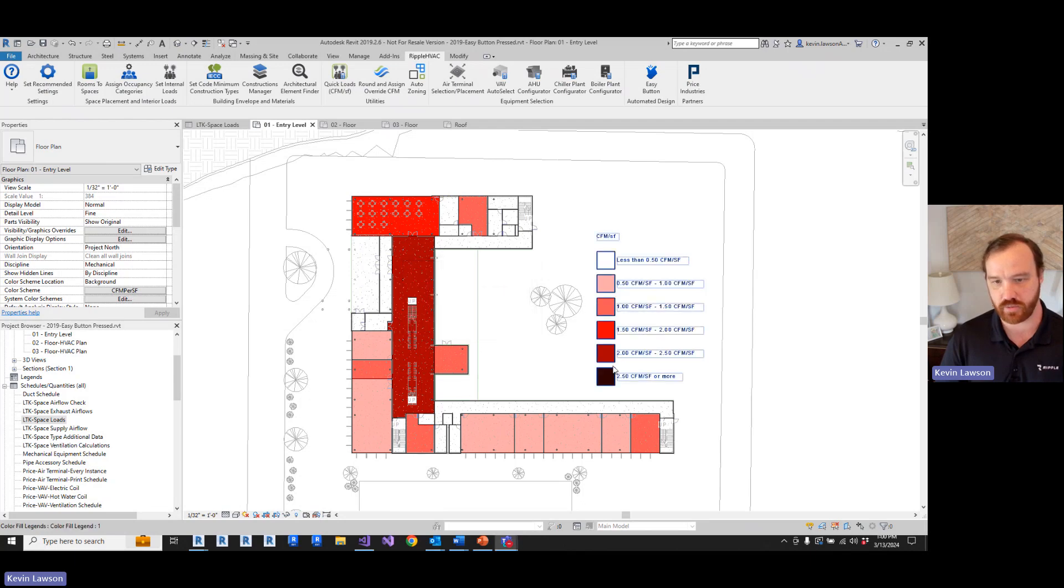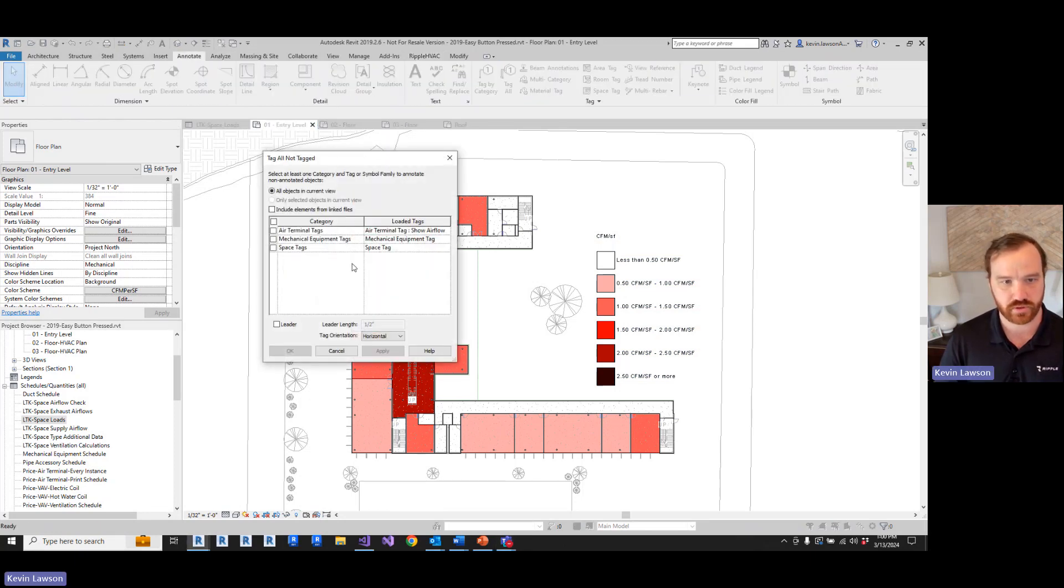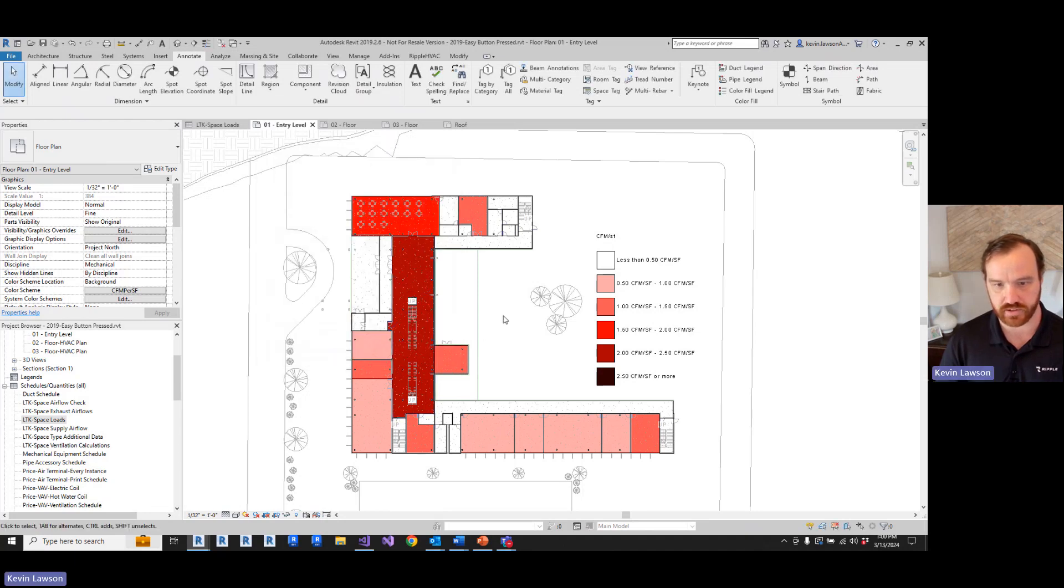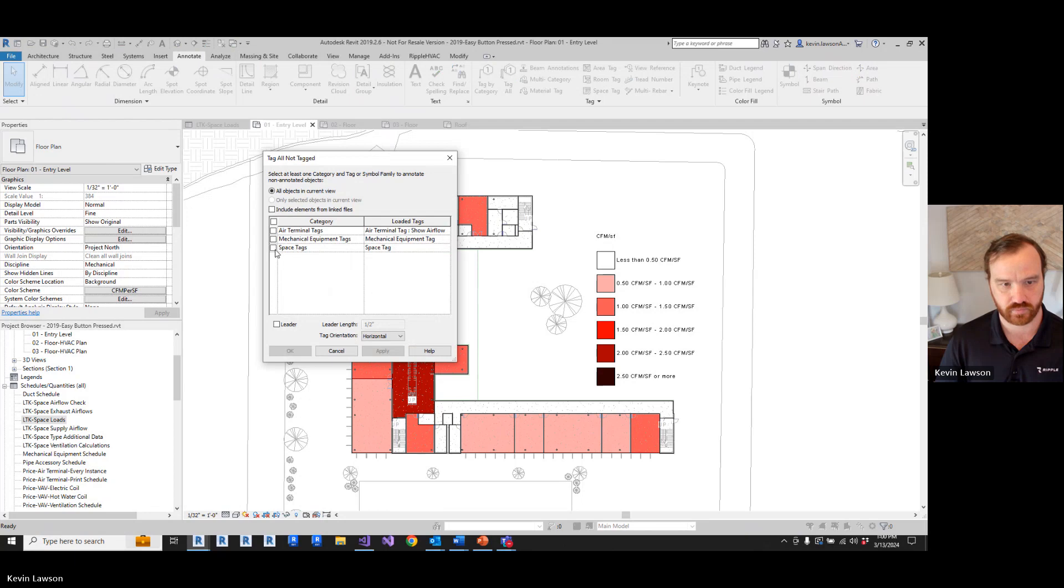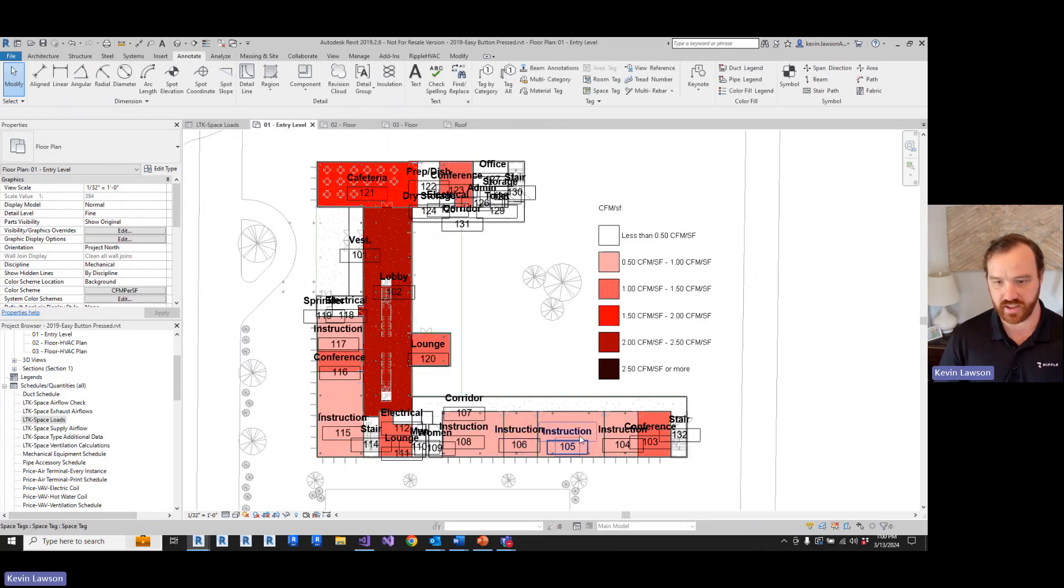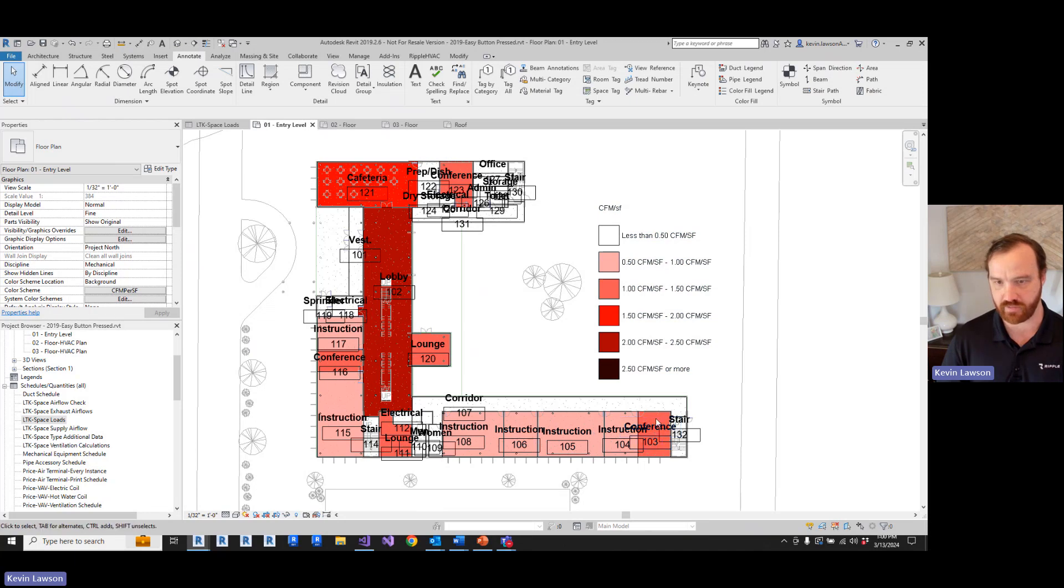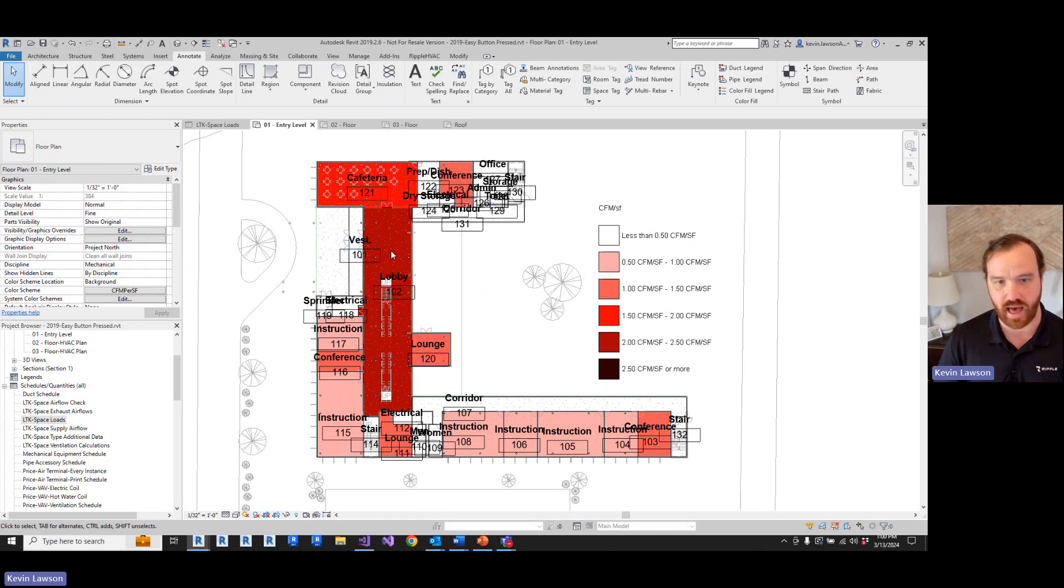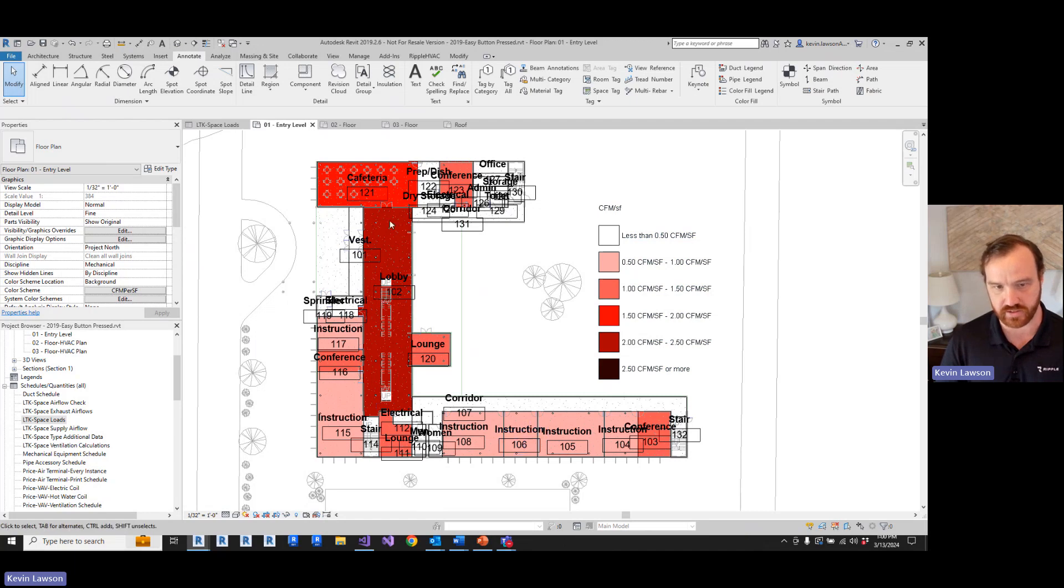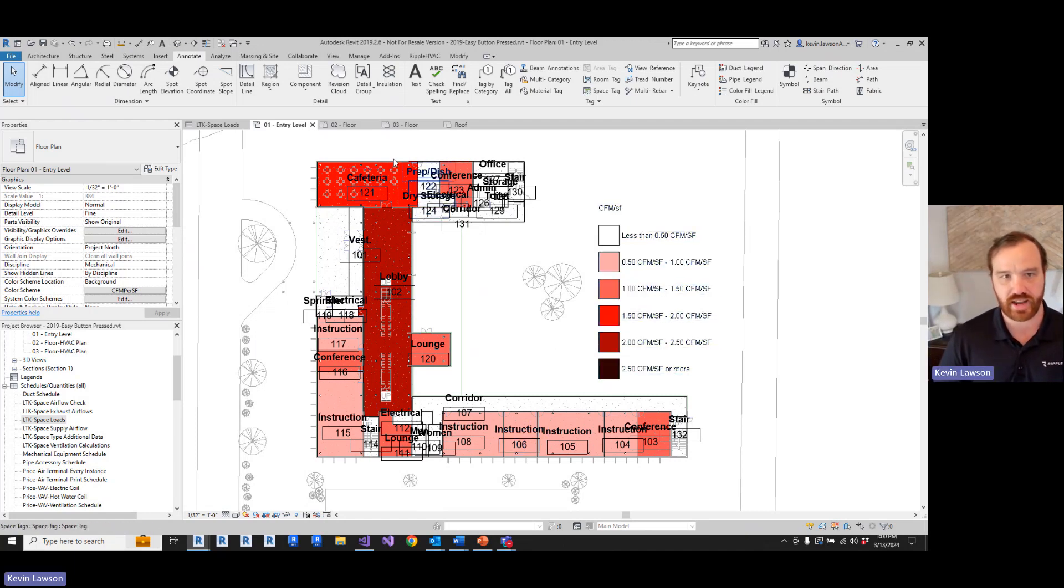But as we can see from the table, it didn't apply these universally. So let's go ahead and tag these rooms. We can see the classrooms went with a little bit less than one CFM per square foot. The conference rooms are a little bit higher. The cafeteria is a little bit higher than that. And the lobby is the highest after that. This is because the occupancy density of these spaces gets higher and higher.